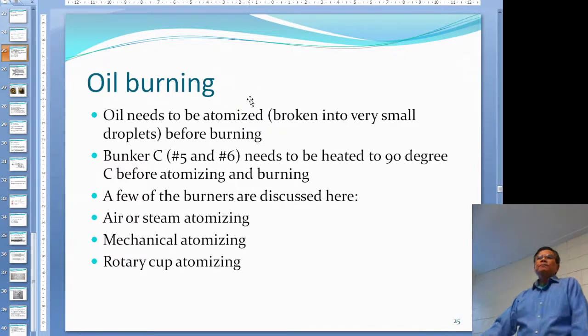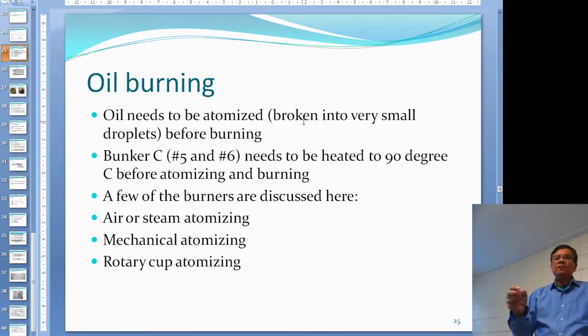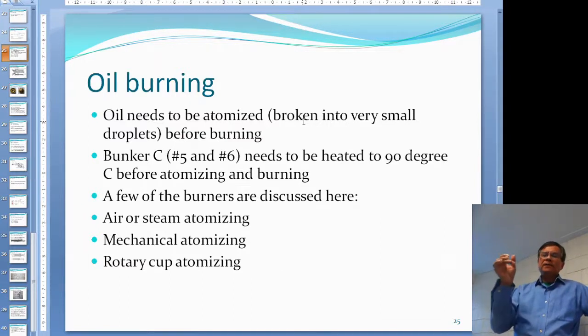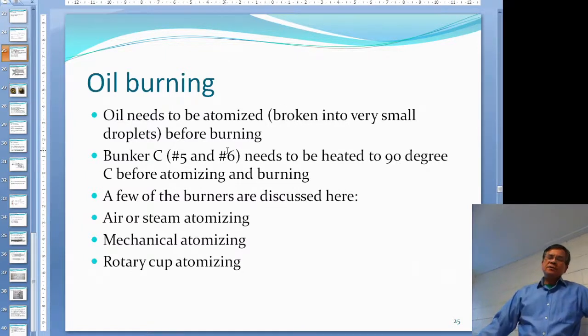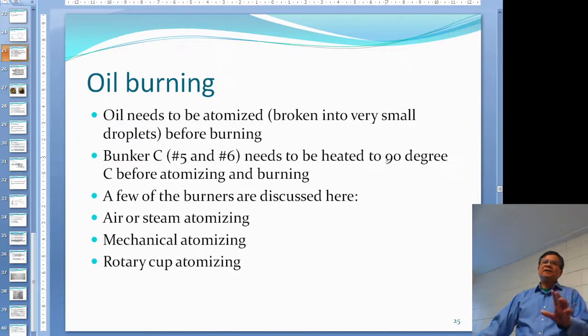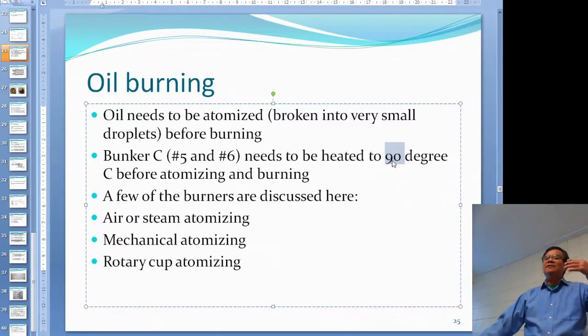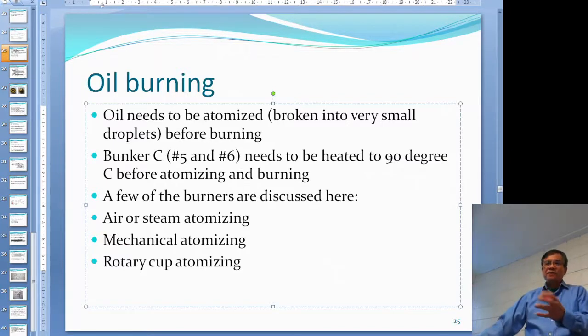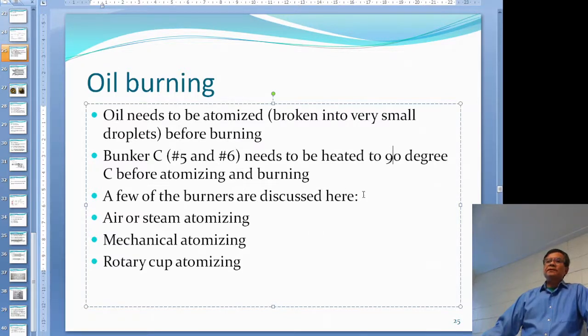The oil needs to be atomized — broken into very small droplets before burning. For #1 and #2, furnace oil and diesel, you don't need much atomizing. But when you go up to heavier oil — Bunker C, grades 5 and 6 — it needs to be heated to around 90 to 95 degrees C before it can be atomized. There is no definitive number; some books say 95, some say 90 — it depends on your situation. There are quite a few different types of burner designs.